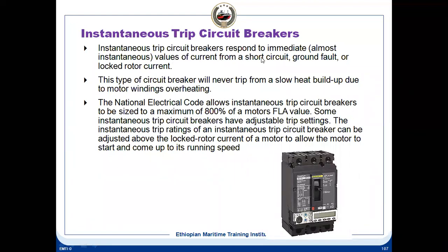Instantaneous circuit breakers respond to immediate values of current from a short circuit, ground fault, or locked rotor current. Locked rotor current means the rotor cannot turn. So at that time, how much is the current? Immediate trip. This type of breaker will never trip from a slow heat buildup due to the motor windings or overheating. As per the NEC, it allows instantaneous circuit breakers to be sized up to 800% of the full load current of the motors. Some instantaneous type breakers have adjustable trip settings.